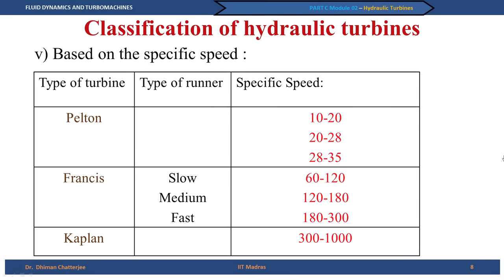The best way of classifying a turbo machine is based on specific speed or shape number. Using the specific speed definition for hydraulic turbines: if the specific speed range N_s is between 10 and 35, we prefer Pelton turbine; between 60 and 300 it is Francis turbine; and above 300 it is usually Kaplan turbine.